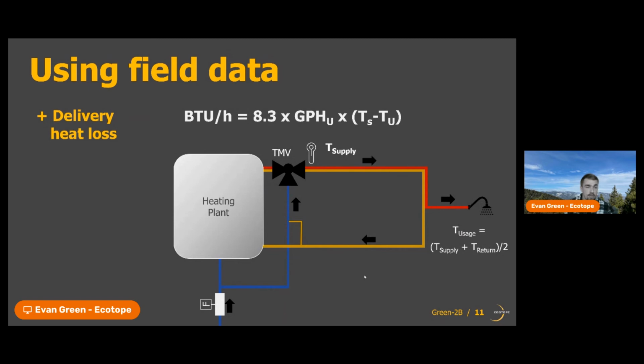So that was the temperature maintenance heat loss, and we're going to measure the delivery heat loss in a similar way, but there are more assumptions attached to this delivery heat loss. We still need a total flow that's being delivered, as well as a temperature differential to plug into this equation. But the temperature that is a little tricky to get sometimes is this usage temperature.